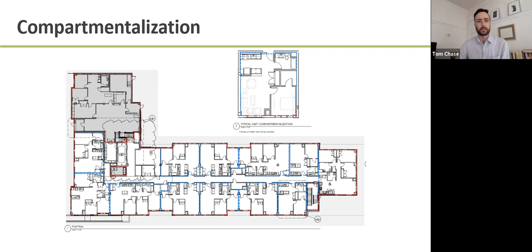So for folks not familiar with compartmentalization testing, here's Zach from our office installing a blower door, just like you would use at the outside for a single family home, but in the corridor at the entryway to the unit, and some of our preliminary test results. I wanted to highlight what those test results look like, because apartments are small, and the smaller your surface area, the harder it is to hit an air barrier test result. Small leaks have a bigger impact in a small surface area.